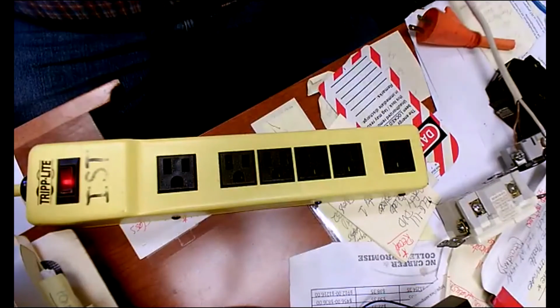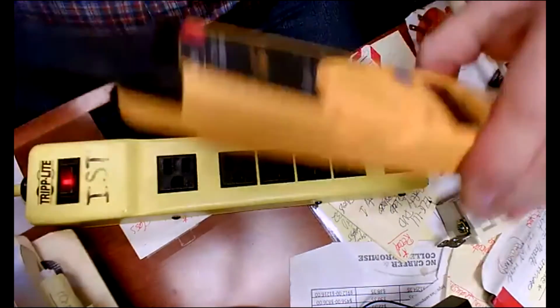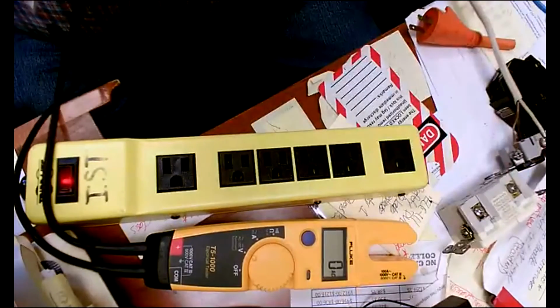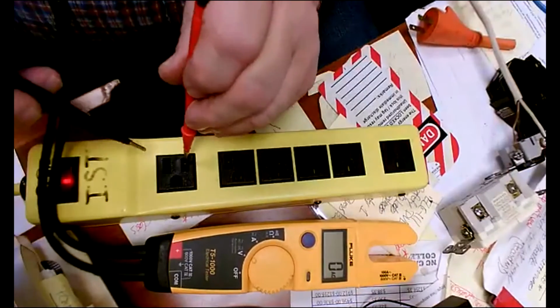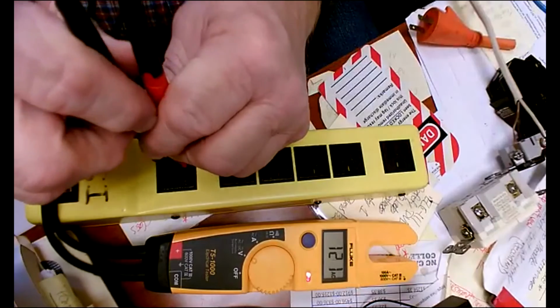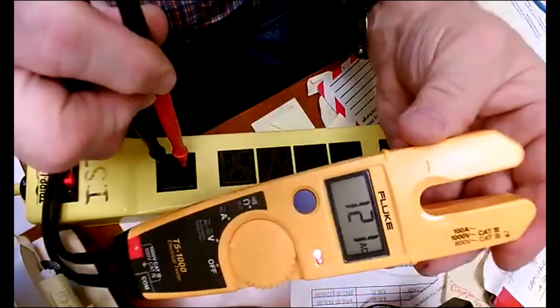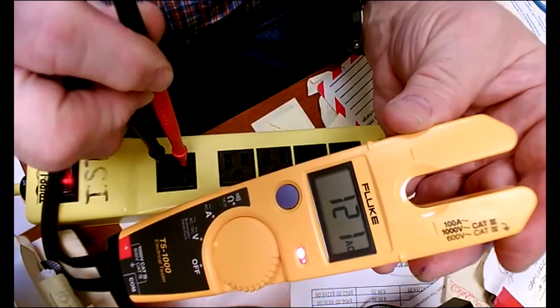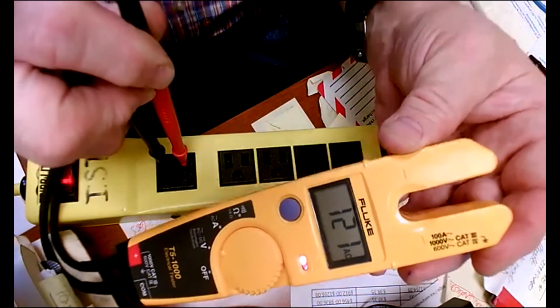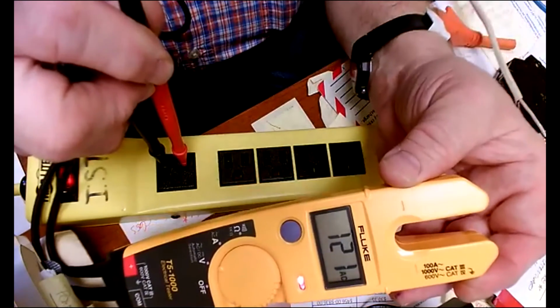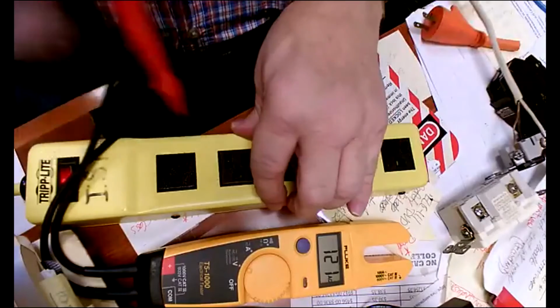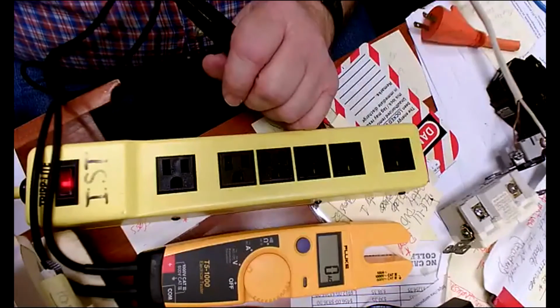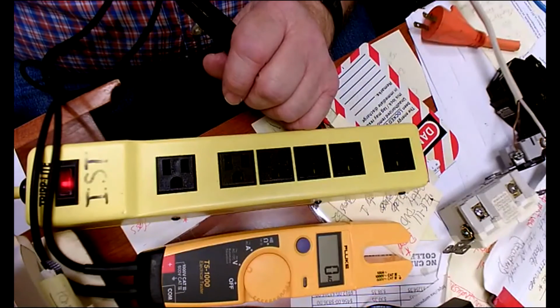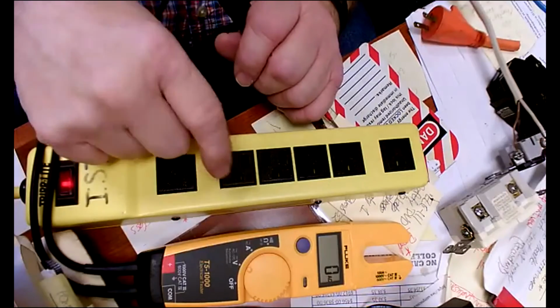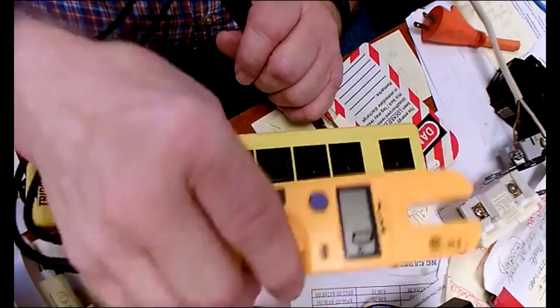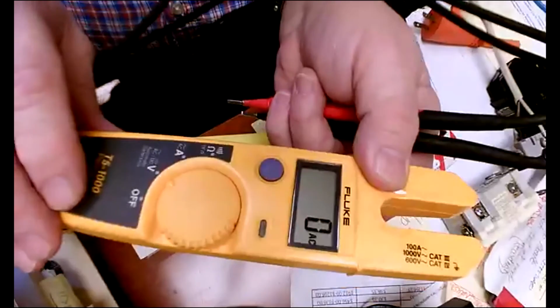OSHA says you go back real briefly, go right back to the same hot circuit that you checked a while ago, and you verify that the meter is still operating properly. And you see that it is, right? Yes, sir. That's a 1, 2, 3 step. You checked it with a known hot circuit. Then you went and checked your breaker on that motor control bucket there, and you saw it was all dead. All legs are dead. Then you came back and checked this one more time. And what that proves is, beyond a shadow of a doubt, that the meter is fine.